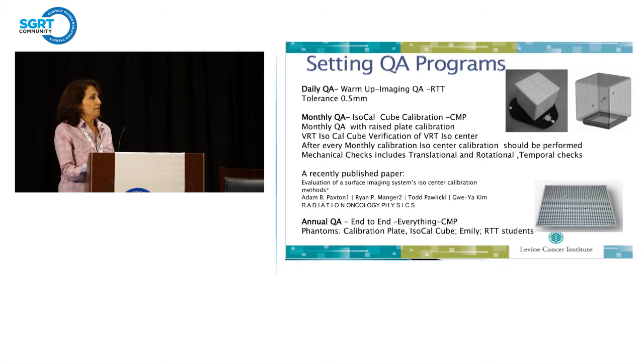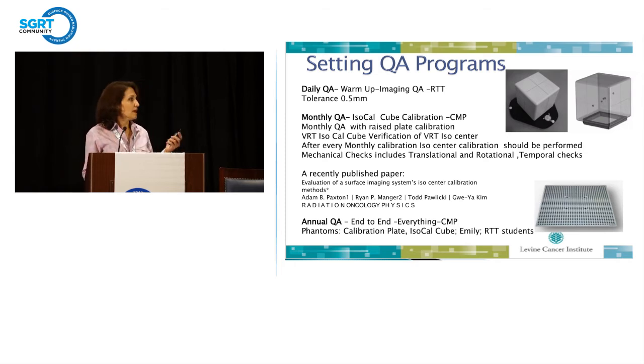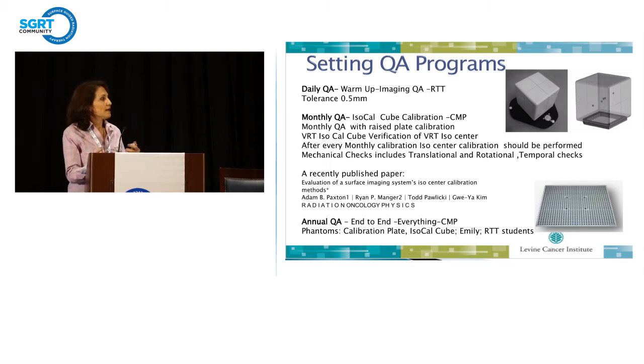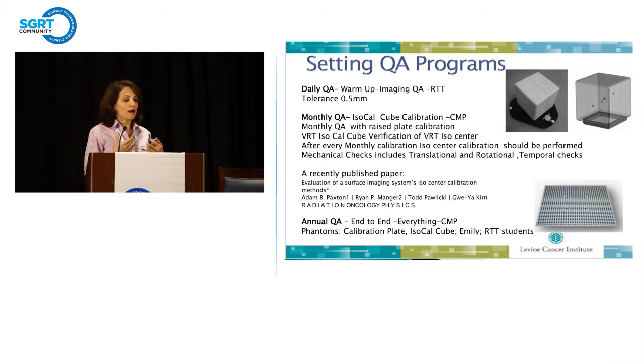So again, daily, the therapist does the warm-up using the plate. And then later on, I integrated Align RT into their imaging QA. We use a modest imaging QA box. And I scan that, and they can do their imaging. While they are doing imaging, they can pull that as a patient, and then they can check. Because when we do OBI testing, and Align RT is a complete system, coming in and warming up, I don't think is just enough.